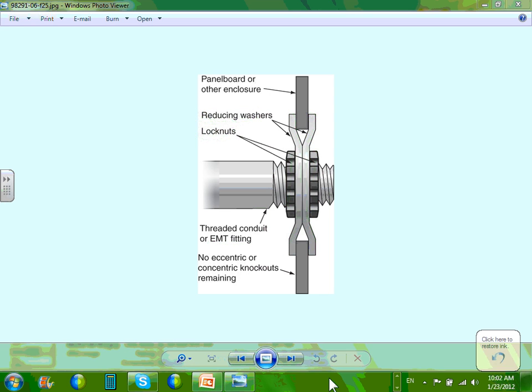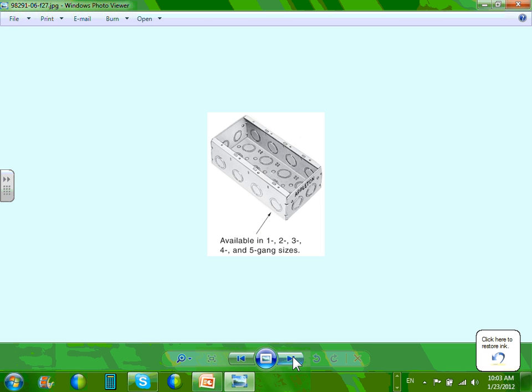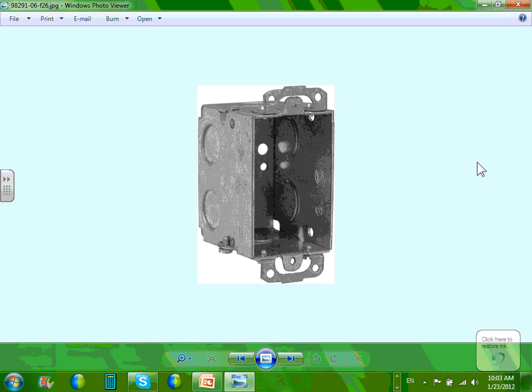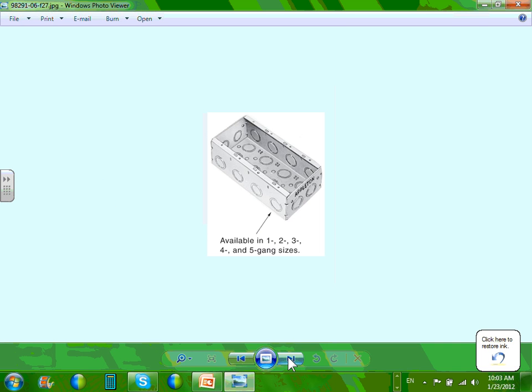I want to spare you the whole equipment bonding, couple of boxes. Most of these boxes, yesterday we were talking about this one, you're going to have knockouts from 1/2 inch to 3/4 inch. Most of the time you can have a 1 inch and bigger knockout. So when you design a box like this, if your conduit is going to be 1 inch, be very careful. You might have to find a special type of box to do it. Make sure when you design a box for receptacles and switches, stay within a conduit of 1/2 inch to 3/4. This is a great design. Otherwise, you might have to find a special box for it.